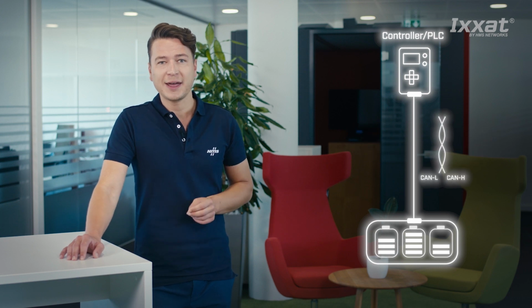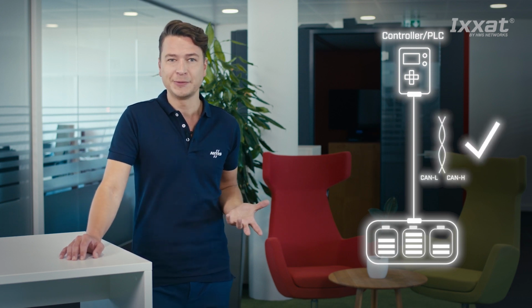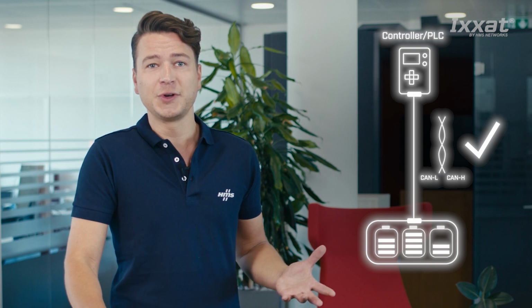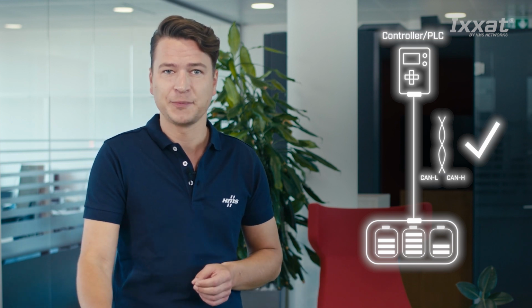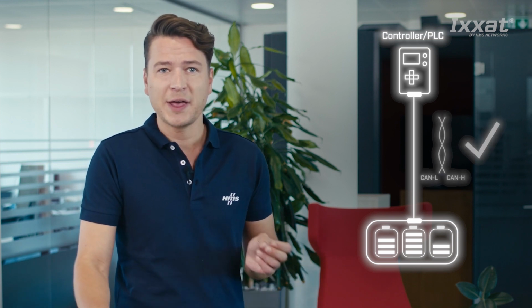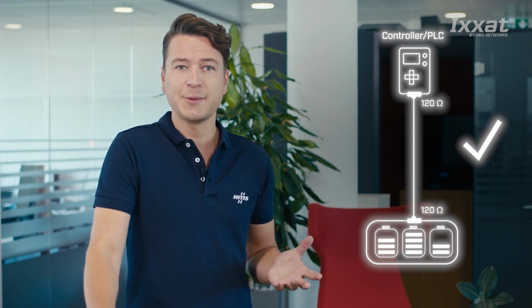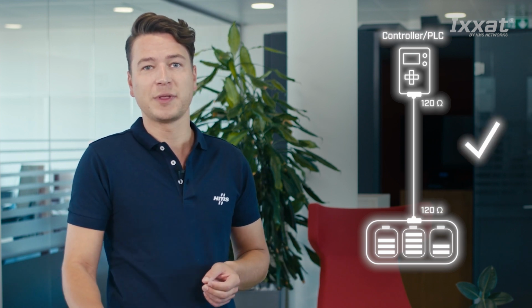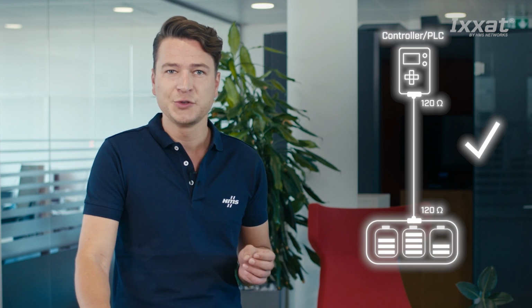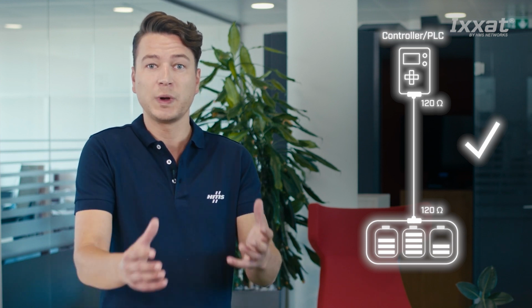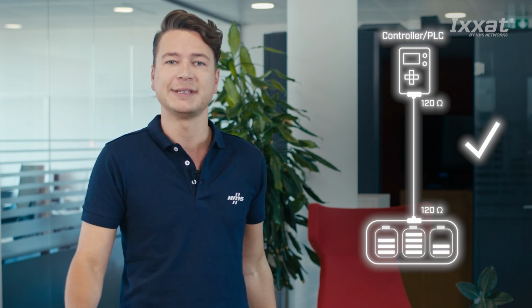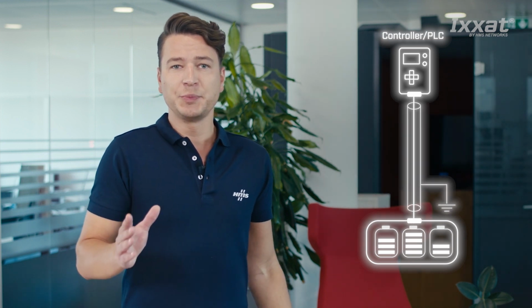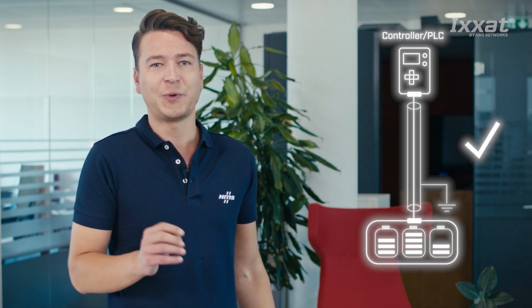Use a twisted pair for both CAN high and CAN low. This minimizes the external electromagnetic influences. You must also consider the method of termination. The cables must be terminated at both ends with a 120 ohm resistor to avoid signal reflection, which will impact the signal quality. It's also important to ground the CAN shield at one side to avoid ground loops.